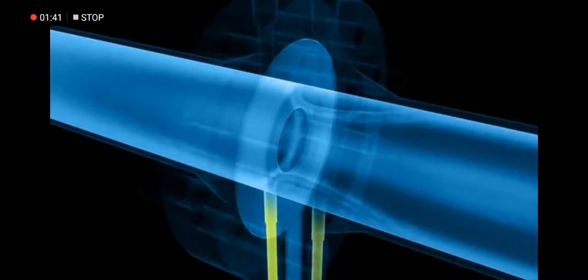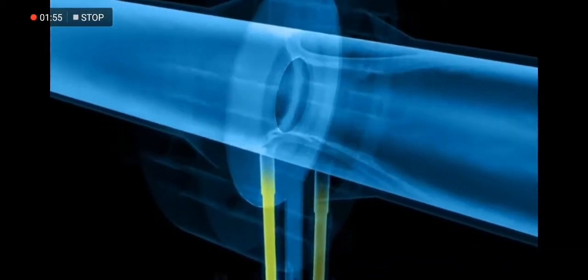As soon as the fluid starts to flow, its velocity around the orifice plate increases significantly because of the restriction in the cross-section. At the same time, due to the laws of fluid mechanics, the static pressure at this point decreases.